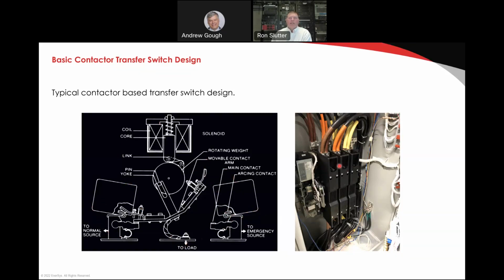This is what they look like today. On the right-hand side, this is the internal workings of a typical contactor-based ATS. So very compact, very simple to see that each one of these is a single phase. In this case, it's 480Y277. How do I know that? I know that because of the color of the wire is an industry standard that we follow. So it's a generic principle by which we can tell the voltage sometimes. Not always true, but it's very typical in the industry. You can see we have the ground down here on the bottom right, which makes this a solidly grounded 3-pole ATS. Okay. We're going to talk about that a little bit later.